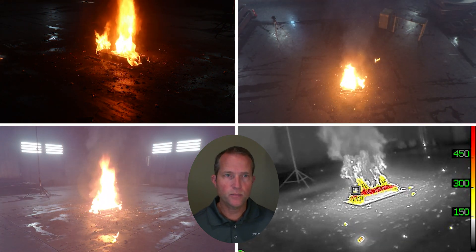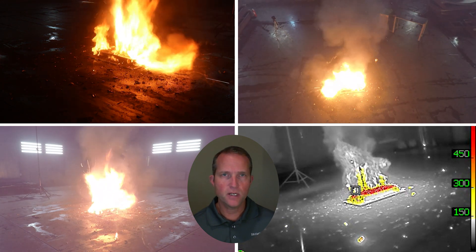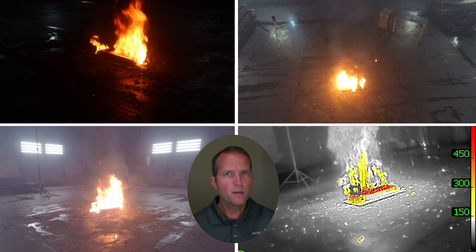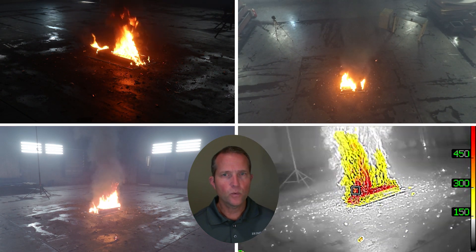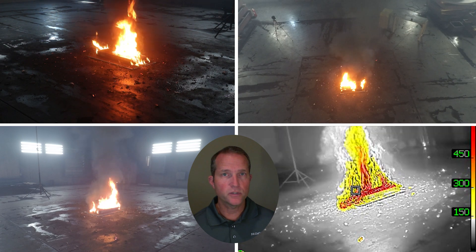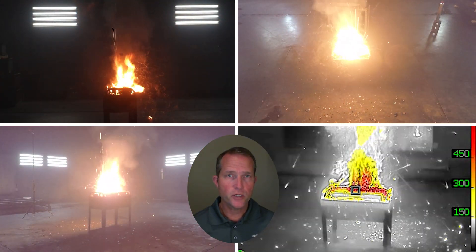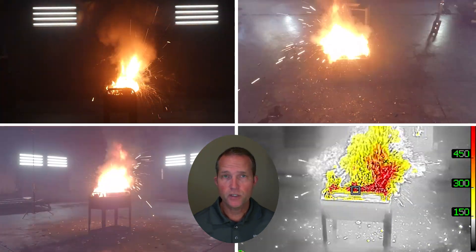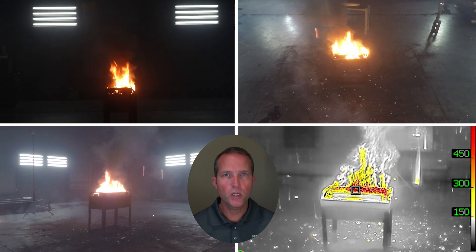Also notice the large flames, showers of sparks, and ejected batteries that are very common in these types of fires. The test facility is a large open space made of concrete, but if these fires were left to burn freely, it's very likely that a fire will spread to other combustible materials nearby. In those videos, we didn't do any sort of intervention with a blanket or any water to try to put those fires out — we simply were doing baselines to understand what a freely burning battery module would look like.